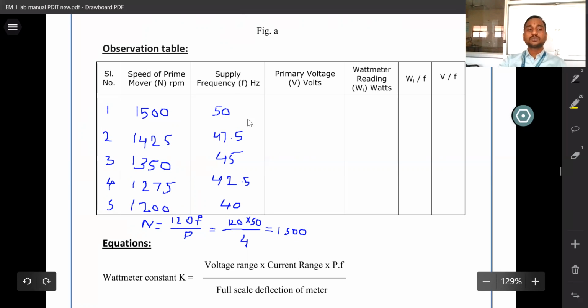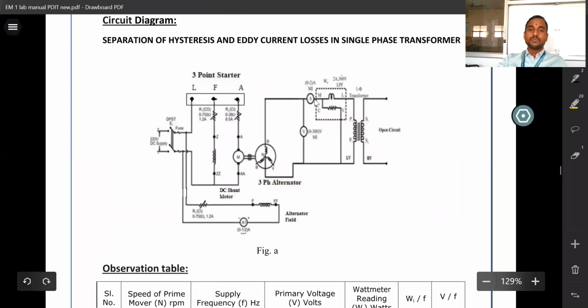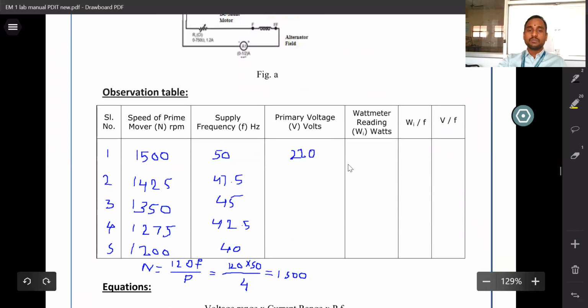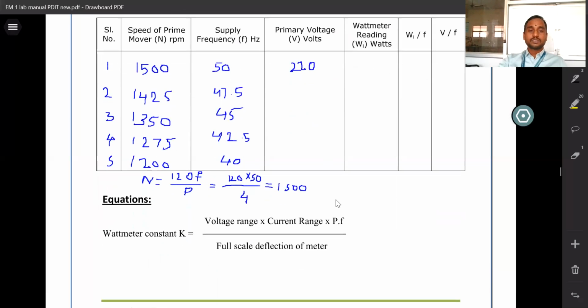So first you note all these things. According to this, you apply the speed of the machine, and the corresponding frequency can be matched. For this particular 50 hertz, you check the primary voltage level. Nearly it is 220 volts, you will get some 220 or 224 volts. You will get the corresponding wattmeter reading, in terms of 30 watts, 34 watts, 35 watts, like that. Note down all the readings of voltmeter, ammeter, and wattmeter from the multifunction meter. So this is the observation table.